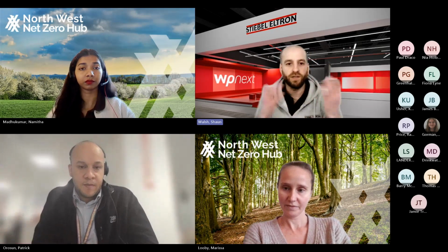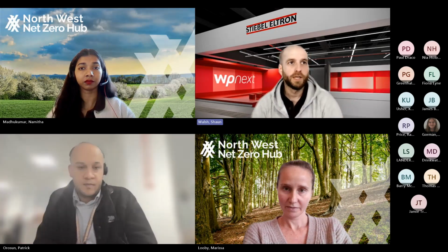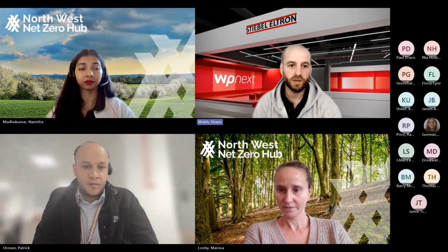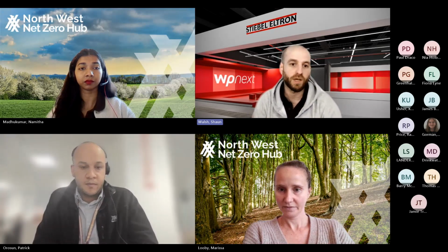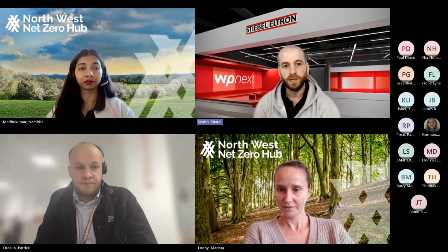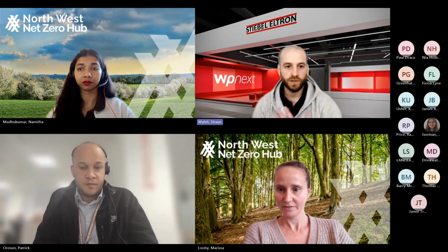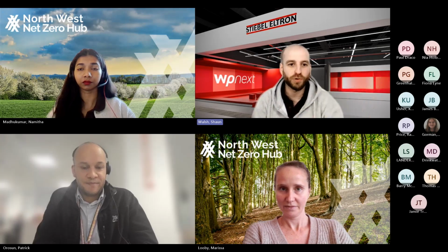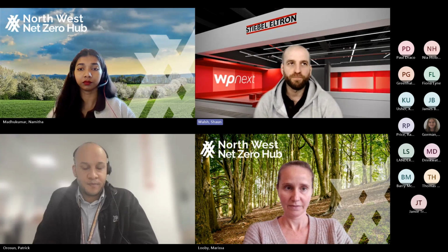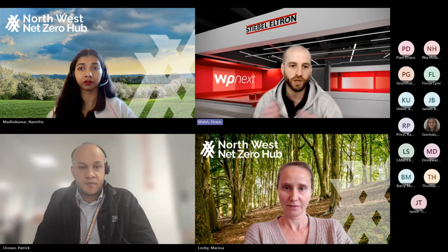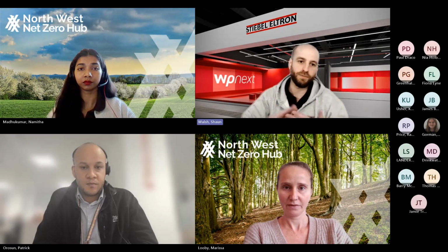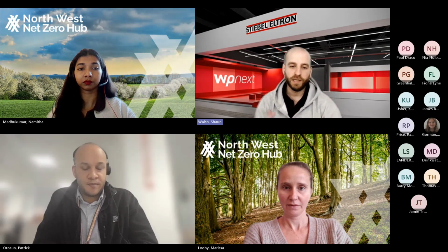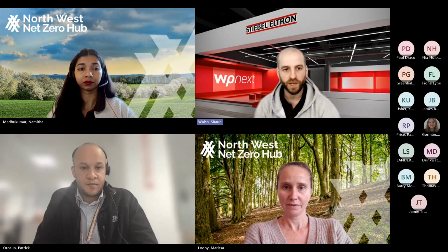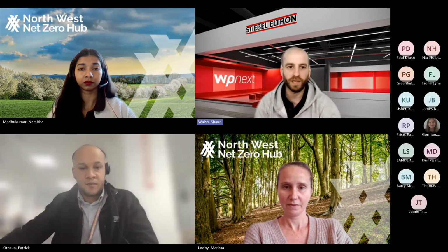Yeah, so I can tell you from my experience from working at Stiebel Eltron how we do it. Typically, whoever installs the heat pump, the initial installer, will offer the customer a service package, and they will carry out the annual service for them. When we do servicing ourselves as a manufacturer, typically we get people who have been abandoned by their installer. Their installer's gone bust, or is no longer available for them, and that's where we would step in. Our service package, for example, includes parts. So part failures are included free of charge, within the cost. Obviously we include our engineers' time, things like that. So the packages vary, but generally it's taken care of by the installer, and we will generally take care of anyone who's been left in the dark, really.